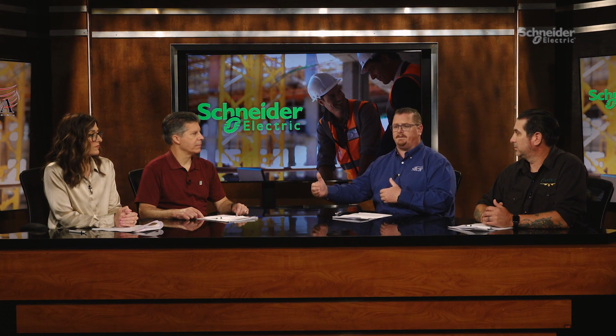This can become specifically difficult if you're in an area where the electrical equipment is outside and you require that working clearance and you're up against maybe a property line where you don't necessarily have control over the entire working clearance because it extends into an adjoining property. So it's something we need to be aware of during the planning stages as well. Yeah, a big concern of mine because I'm in California and all our switchgear is outside because we've got great weather. Yeah, you can think of some areas though where the land really rolls, it can be a worker safety issue to make sure that you have the space so someone can work safely.